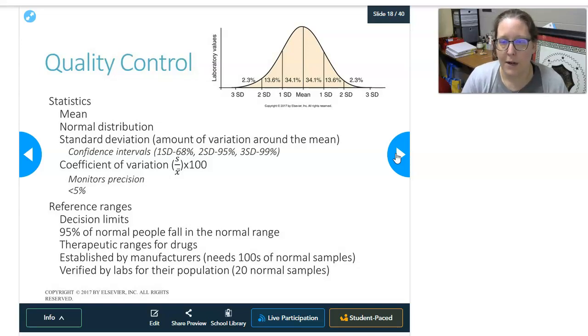All right, so let's talk a little bit about statistics. I did mention that the quality control range is usually calculated as the mean plus or minus 2 standard deviations. So these are statistical variables that can be calculated. To get the mean, you add up all of your results on that specific analyte on that specific quality control level, and divide by the number of results. So if you have 30 days and 30 results, you would add all 30 values together and divide by 30, and that would give you your mean.